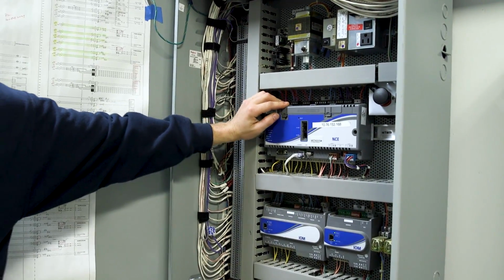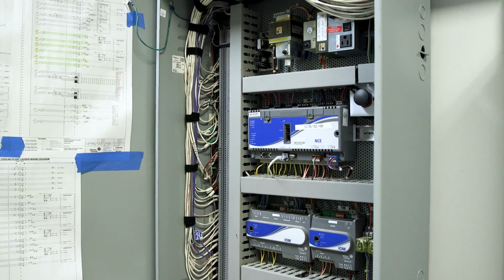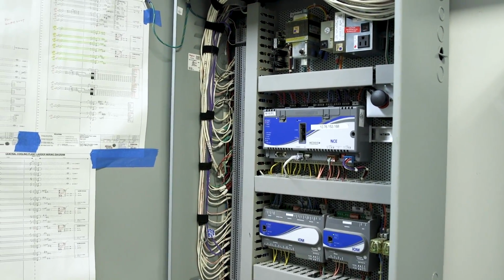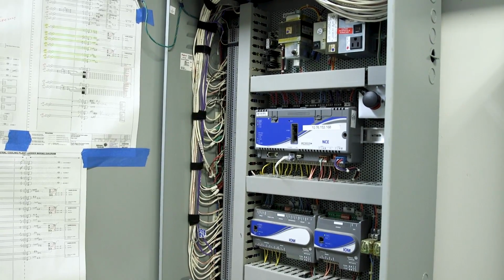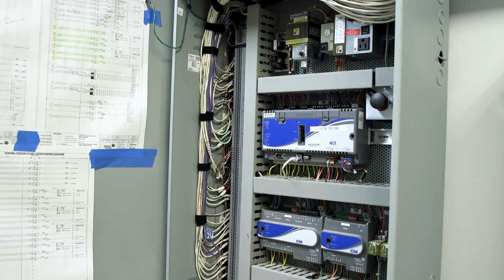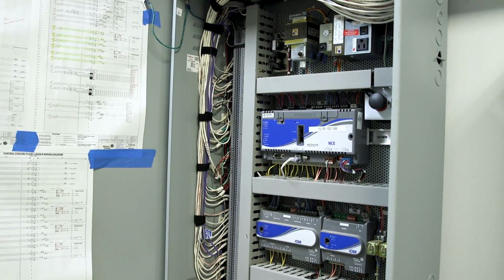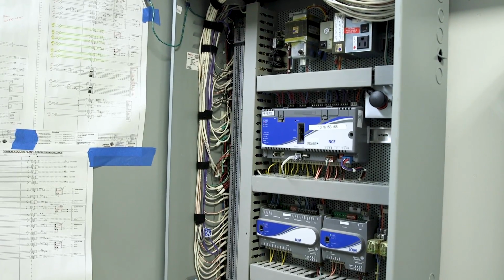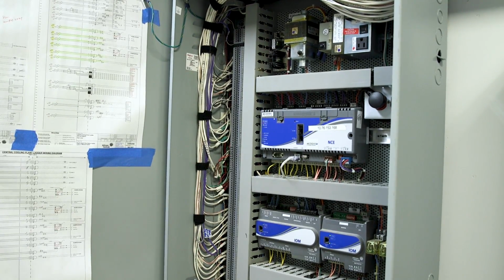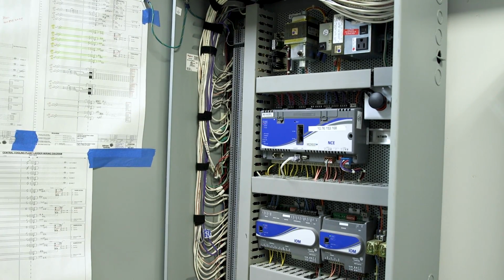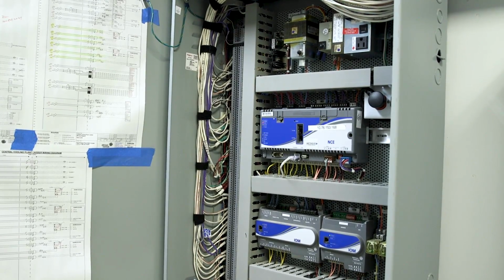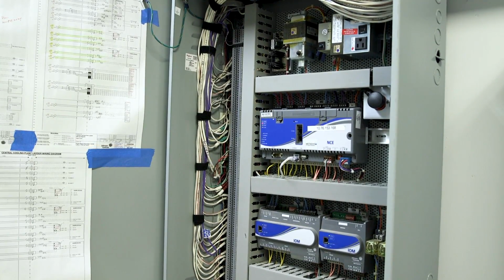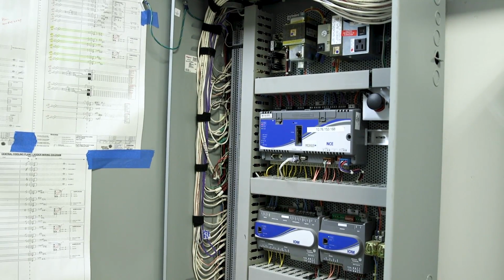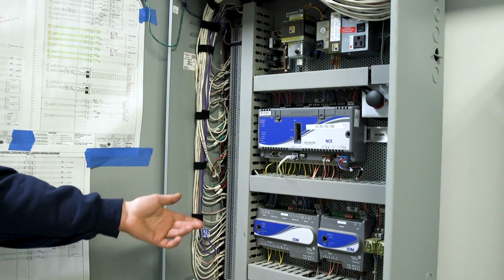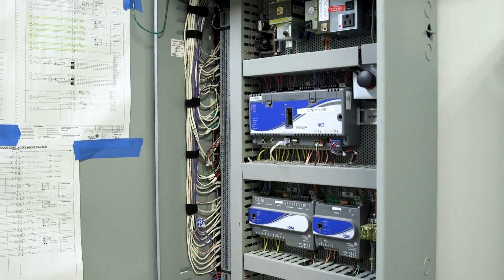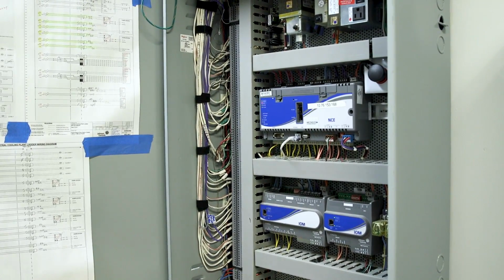Is there really any case, it sounds like a dumb question, where it'll be a point overload for the NCE? As far as an overload, what do you mean by overload? Like it's run out of points? Yeah, when it has no space for, say, a particular point. Like you got your BOs and your AOs, and then all of a sudden it feels like it's picking up more points. No, because you have to define where your points go on the list. Okay. So if you have a BO but there's no BOs available, you could use a CO. But if a CO is not available, then you're going to have to add another controller, which would be an IOM. All right. But you have to add those in the list actually in software in the CCT program. You can't do that from the head end.